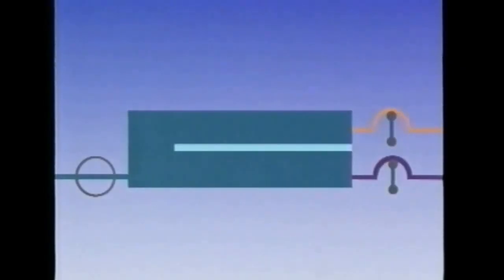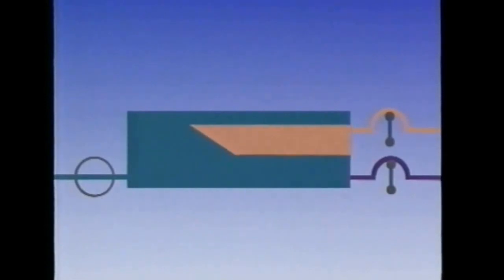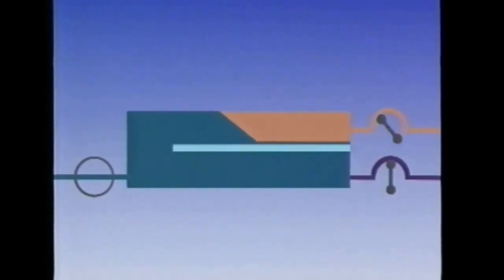At the start of the separation process, the barrier is inflated, hence the cells accumulate below it. After a predetermined time interval, the barrier is deflated to allow the cells to move to the top of the bladder. The barrier is then re-inflated before these cells are drawn off through the top outlet.